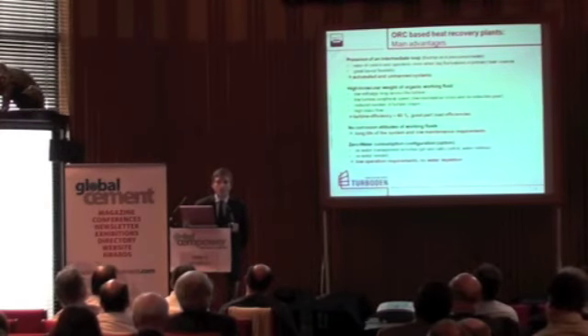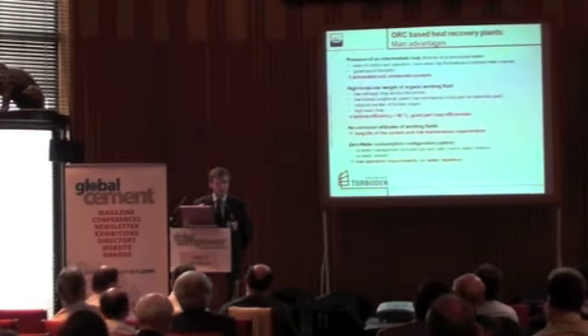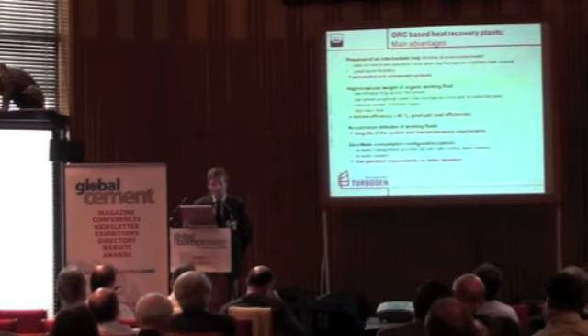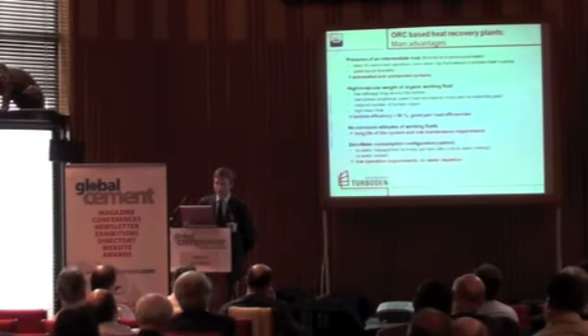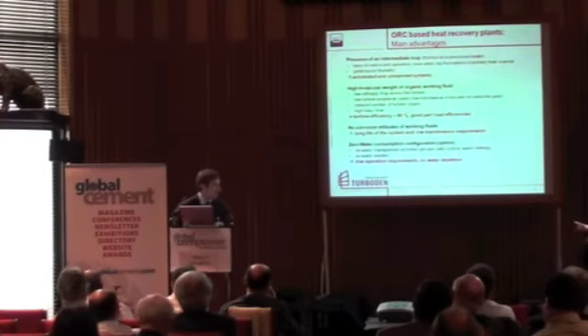You can think that a steam turbine with 15 stages or 10 stages, when running at half of the load, is definitely not optimized, especially the last stages, which may suffer quite inefficient working points. We have just maybe 2 or 3 stages, and even at part load, the working condition of the last stage is not as bad as the very last stage, the 14th stage, of a steam turbine. This is a general consideration. We shall go into the fluid dynamic details to address these points, but take it as a qualitative indication. Okay, we have some other questions.